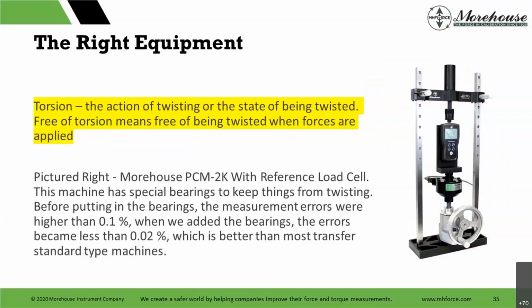Torsion, the action of twisting or the state of being twisted. Free of torsion means free of being twisted when forces are applied. When we first built this, there's a note at the bottom pictured right. We first built this machine, our torsion error was like 0.3%, just way too large. What was happening here is we have screws, and as we try to pull things apart, they're twisting. In compression, we didn't see it as much, but we did see it.